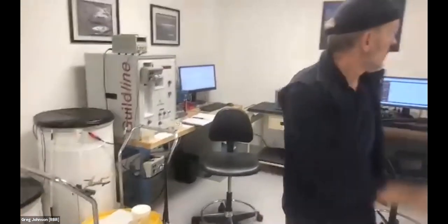Great. Some other area with linearity test, if you're interested in that part. So usually before the conductivity calibration occurs, we prove to ourselves that the conductivity cell is linear. And it's one of the questions that occurred in the earlier webinar, whether you can use our conductivity cell in fresh water. You absolutely can, because the inductive technology is linear over the full range. We prove that as it's part of the design, but we prove it as part of the calibration process.